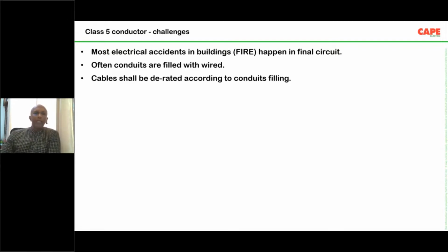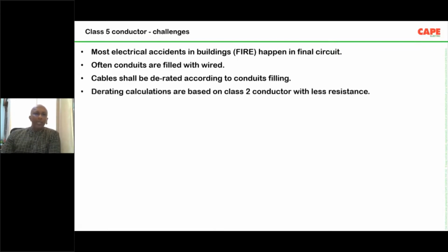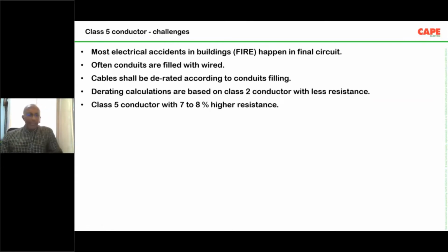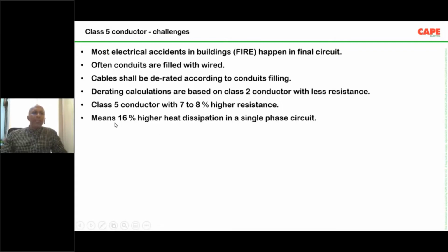All the derating factors are based on class 2 conductor. Whereas in India, we don't use class 2 conductor, we use class 5 conductor. Since we use class 5 conductor, the heat is about 7 to 8% higher, because the resistance of the conductor is about 7 to 8% higher in our wires. In a single phase circuit, with a line conductor going and the neutral conductor coming back, approximately 16% higher heat dissipation will happen in the conductor. What happens? 16% higher heat means higher deterioration, higher degradation of the insulation, and finally fire.